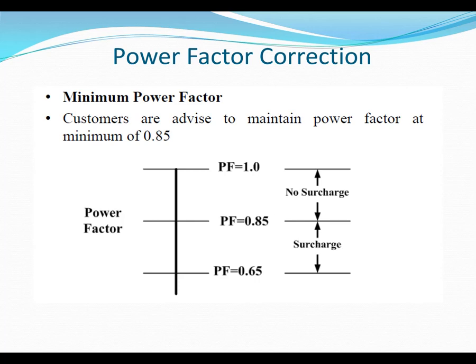TNB will impose a surcharge on a customer whose average power factor is lower than 0.85. If our power factor is lower than 0.85, we will be charged by TNB — we have to pay a penalty. This applies to medium and low voltage consumers.